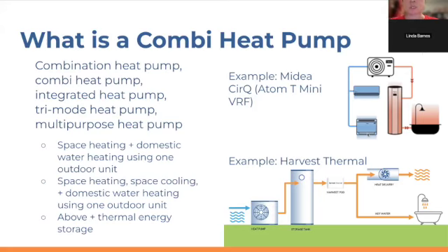Harvest Thermal uses a system that utilizes a CO2 heat pump on the outdoor side. And we'll talk about this more, but one of the caveats of a CO2 system is that for now, the CO2 technology in the residential sized outdoor units doesn't do cooling. And so it's a heating only system. Not to say that CO2 systems can't do cooling. I mean, there are many supermarket refrigeration systems that are CO2 based, so they can definitely do cooling. But yeah, the products in the residential heat pump market haven't gotten there yet.